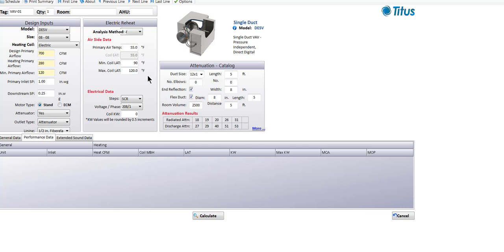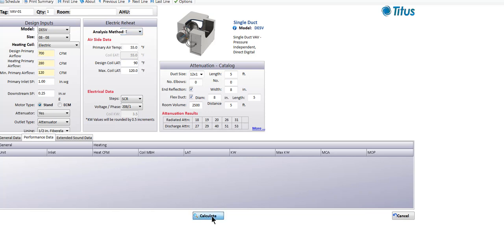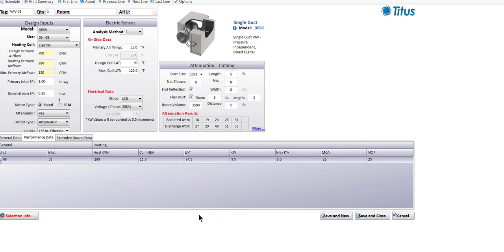We've never heard of anyone having electrical problems due to these heaters in their buildings. So if we were going to select a unit with 90 degree leaving air temperature, 55 degree entering air temperature, and 280 CFM as our heating flow rate, we can make a selection. Going with leaving air temperature selected at 90 degrees, it came up with 11.9 MBH, which corresponds to 3.5 kilowatts. It gave us a leaving air temperature of 94.5 because the program works in increments of 0.5 kilowatts, so it gave us a little bit more heat than we wanted.